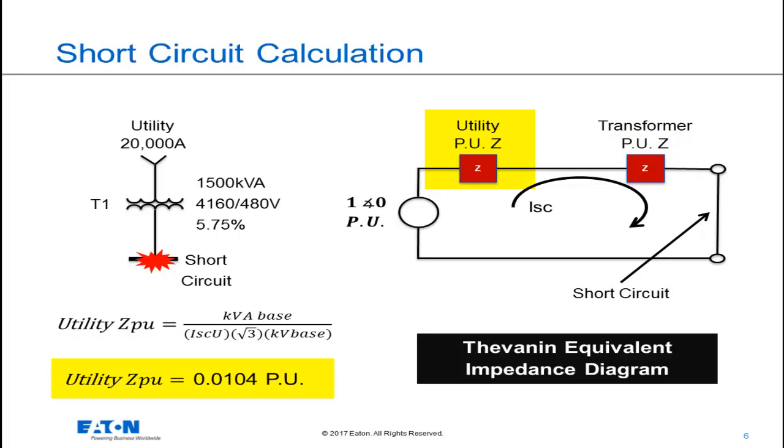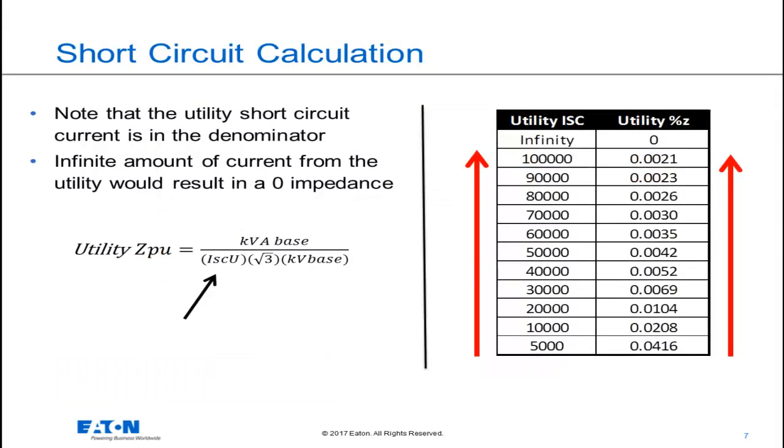The utility impedance in per unit can be calculated by the basic equation shown here. So based on this equation, the impedance for the utility in per unit is 0.0104. The short circuit current from the utility is in the denominator of this equation.